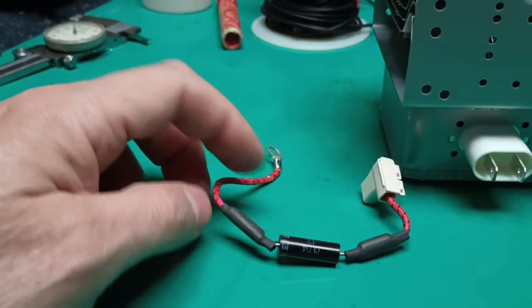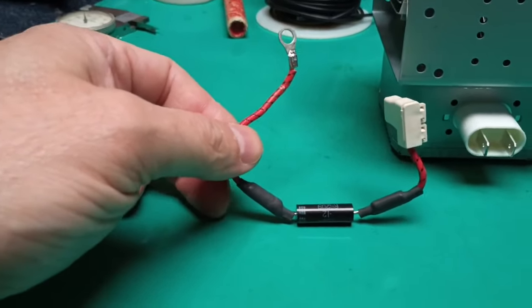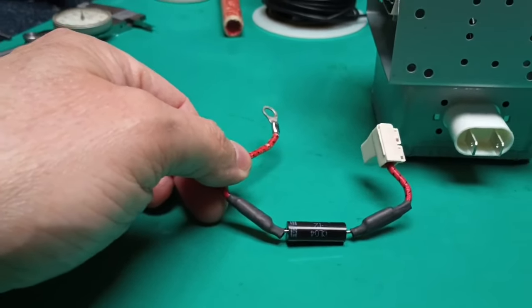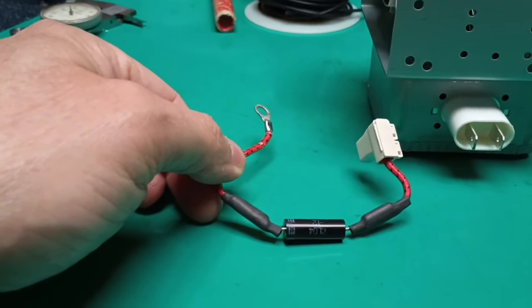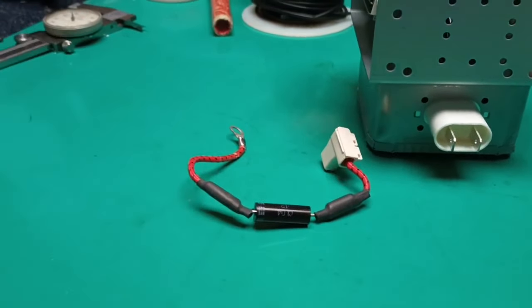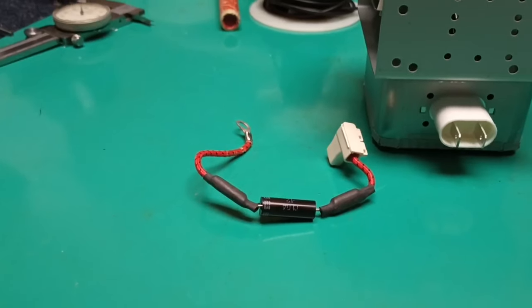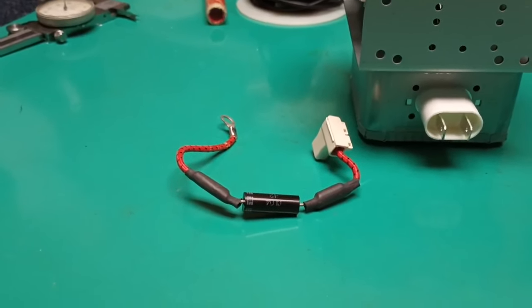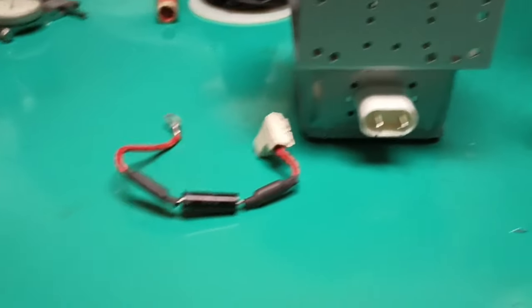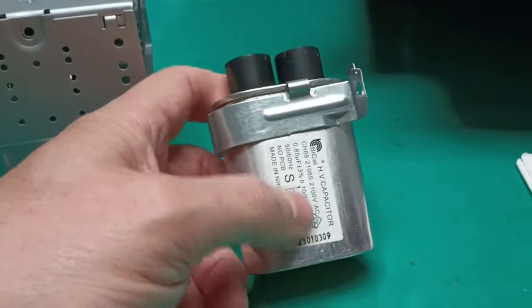Here's the rectifier assembly. There are multiple rectifiers inside. I cannot read it with my DMM on diode test scale and that's 10 volt max. So the forward drop of that is probably more than 10 volts. So there may be six or eight or 10 individual diodes inside there. That's done for high voltage. If each one has a drop of a volt, then there might be multiple adding up to some forward voltage drop. This gets warm in operation.